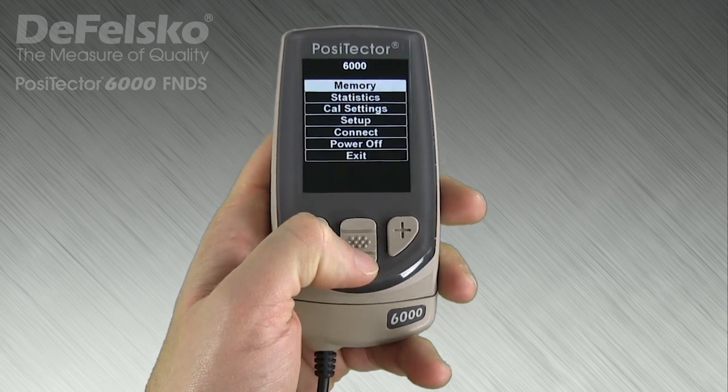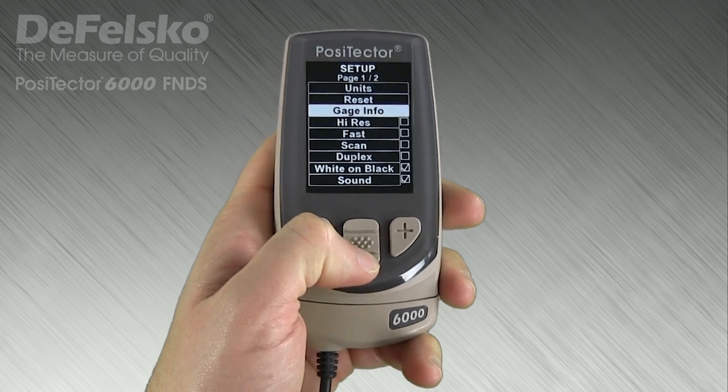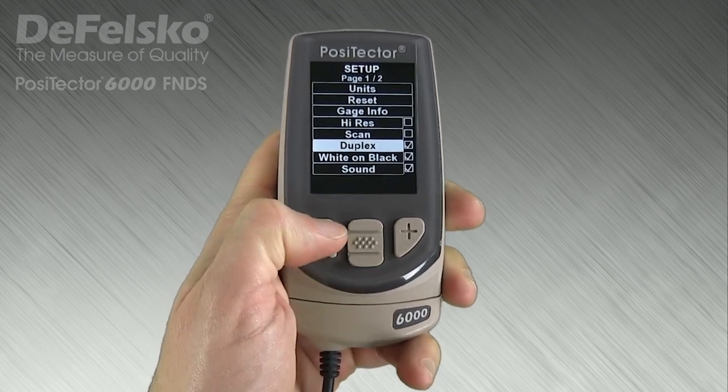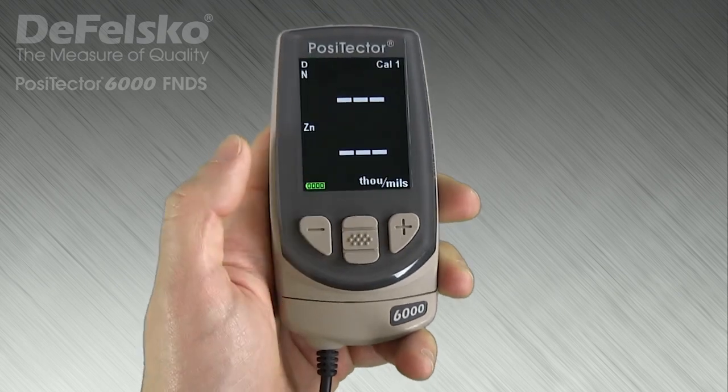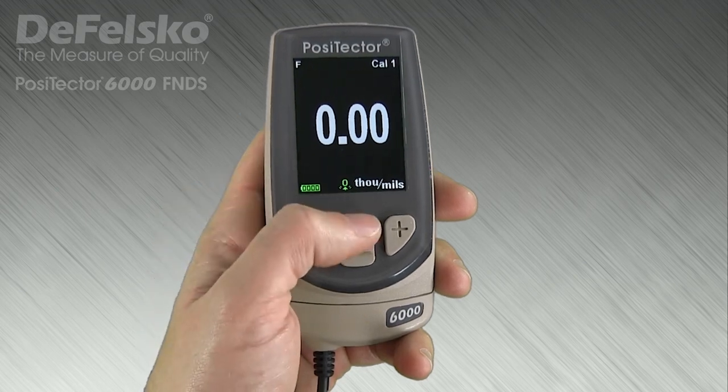Measuring coated galvanizing requires that both operations happen in a single reading. This is performed by selecting the duplex menu option. Alternatively, the up navigation button quickly toggles duplex mode on or off.